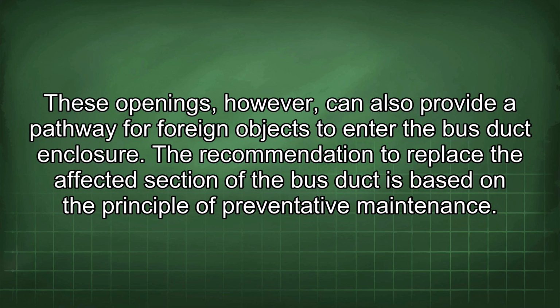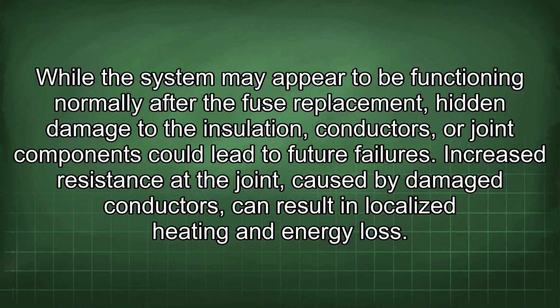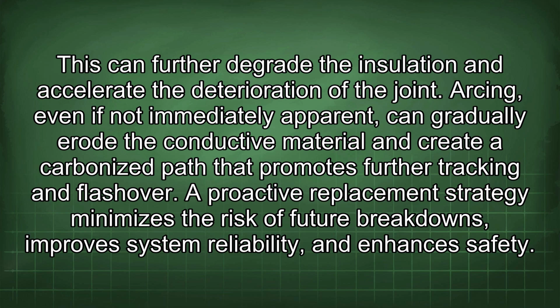enclosure. The recommendation to replace the affected section of the bus duct is based on the principle of preventative maintenance. While the system may appear to be functioning normally after the fuse replacement, hidden damage to the insulation, conductors, or joint components could lead to future failures. Increased resistance at the joint caused by damaged conductors can result in localized heating and energy loss. This can further degrade the insulation and accelerate the deterioration of the joint. Arcing, even if not immediately apparent, can gradually erode the conductive material and create a carbonized path that promotes further tracking and flashover. A proactive replacement strategy minimizes the risk of future breakdowns, improves system reliability, and enhances safety.